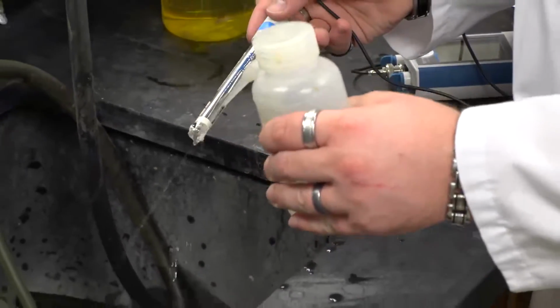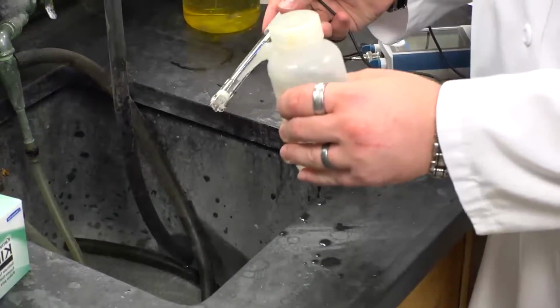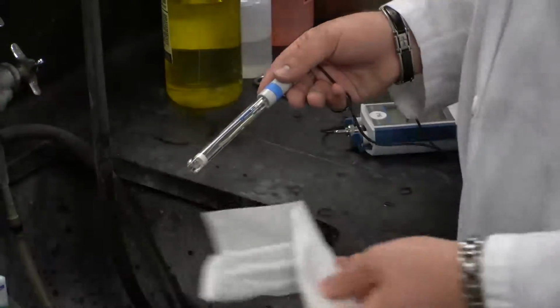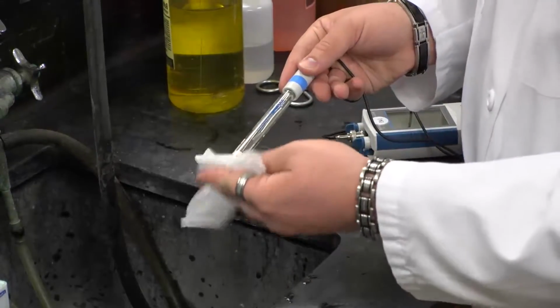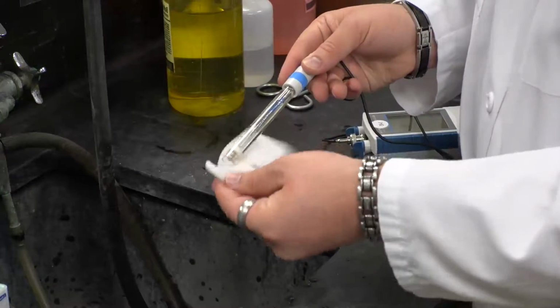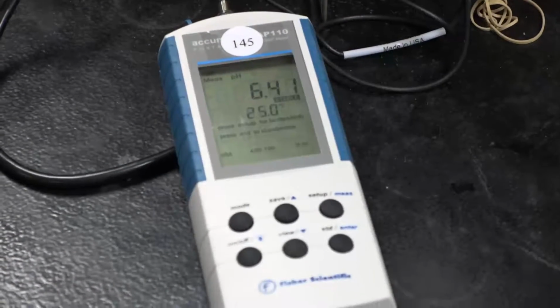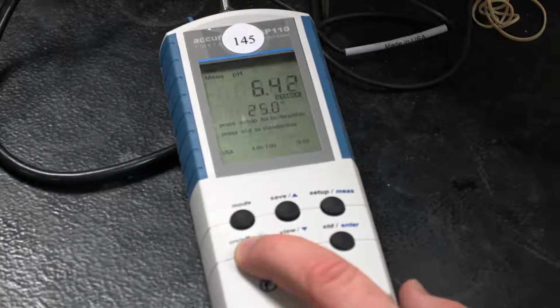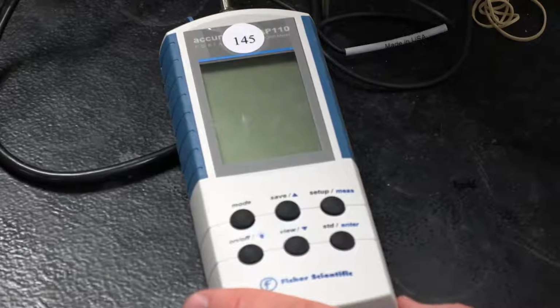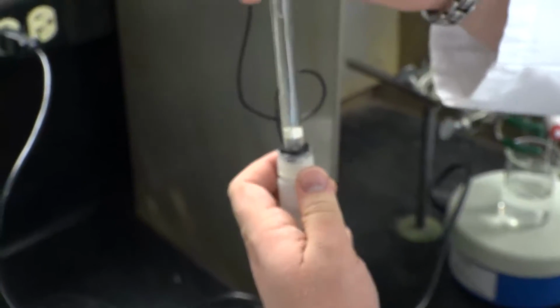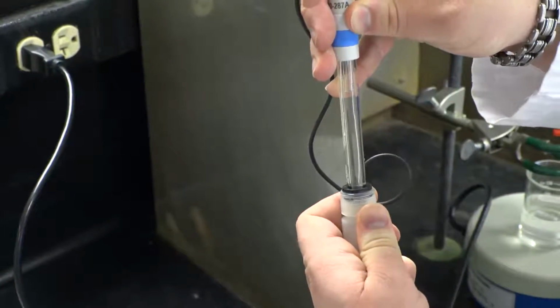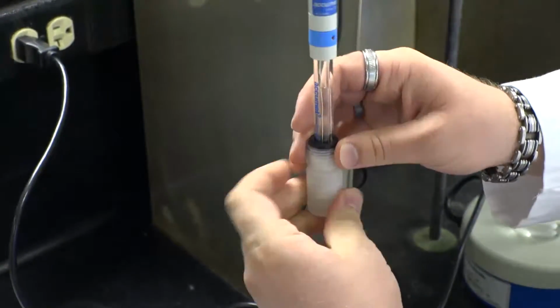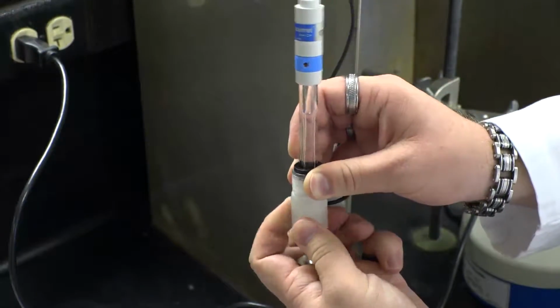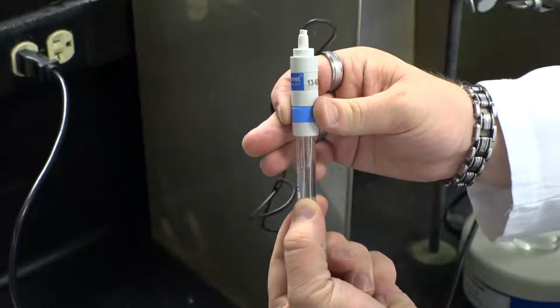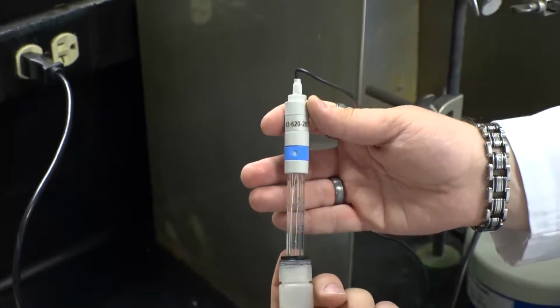Keep in mind that when you transfer your probe to other solutions, you should always rinse the end of your probe with DI water and blot it dry with a Kim wipe before placing the probe into another solution to avoid contaminating or diluting the solution. When you finish using your meter, you will turn off the meter by holding the on/off button until the meter displays off and promptly powers down. Be sure to put the probe back into its original storage bottle by putting the probe through the bottle cap, then tighten the cap back onto the bottle, after also making sure to check that the ring on the upper portion of the probe is turned counterclockwise to the closed position before returning your meter.